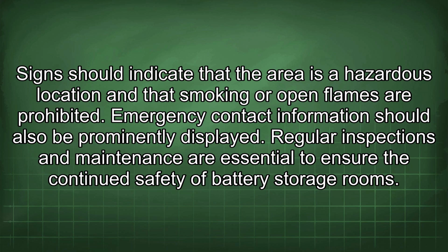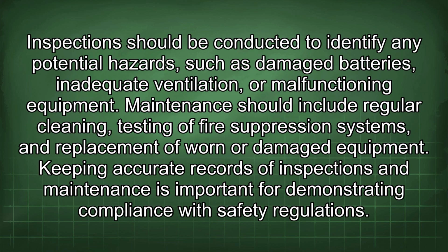Regular inspections and maintenance are essential to ensure the continued safety of battery storage rooms. Inspections should be conducted to identify any potential hazards, such as damaged batteries, inadequate ventilation, or malfunctioning equipment. Maintenance should include regular cleaning, testing of fire suppression systems, and replacement of worn or damaged equipment. Keeping accurate records of inspections and maintenance is important for demonstrating compliance with safety regulations.